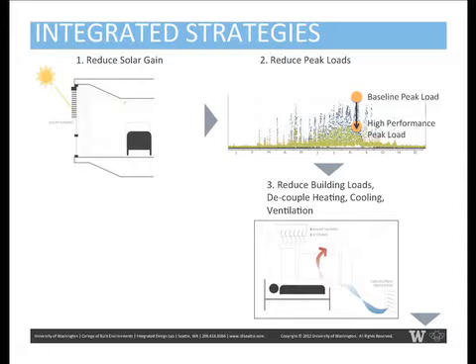So on the left is January through December, and it's looking at the load profile of the building. And what we can see is in green is the high performance, and the blue is the baseline. What we're trying to do is minimize the peak, which means reducing the size of the equipment. And we also want to reduce the area under the curve, which is the amount of energy that's going to be used on an annual basis. So there's both reducing the peak and reducing the area under the curve.